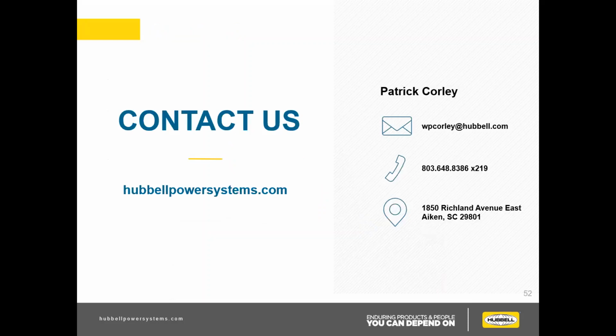The first question we do have, though, Patrick, is what field testing does Hubbell Power Systems recommend for distribution arresters? Sure. So we don't require field testing, first off. We routine test all of our arresters before they leave the factory. So field testing is definitely not required. And that goes for pretty much anyone. Any reputable manufacturer should be designed to be immune to degradation. So most field testing is not required or even recommended. If you feel like you have to do it, our infrared analysis is the most recommended.